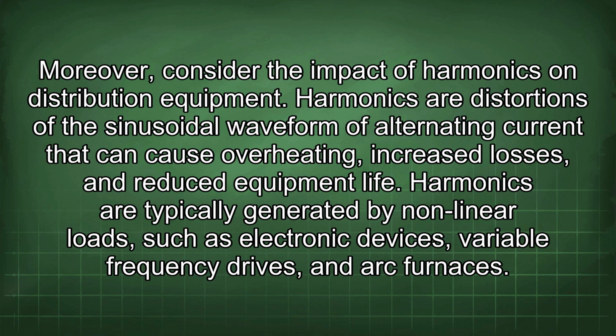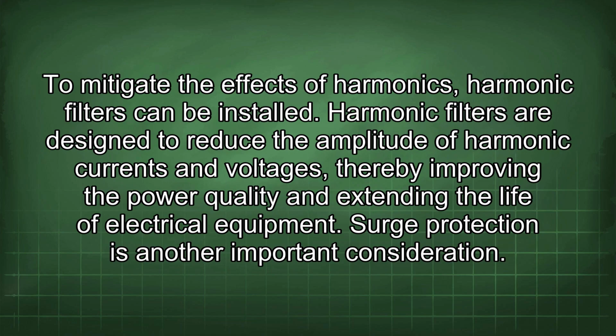Moreover, consider the impact of harmonics on distribution equipment. Harmonics are distortions of the sinusoidal waveform of alternating current that can cause overheating, increase losses, and reduce equipment life. Harmonics are typically generated by nonlinear loads such as electronic devices, variable frequency drives, and arc furnaces. To mitigate the effects of harmonics, harmonic filters can be installed. Harmonic filters are designed to reduce the amplitude of harmonic currents and voltages, thereby improving the power quality and extending the life of electrical equipment.